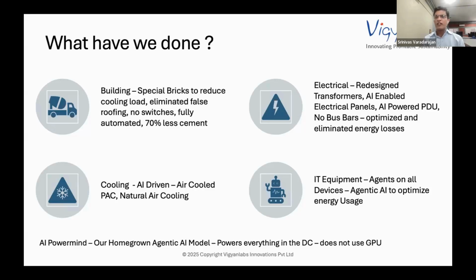All the building data centers had false ceilings. I said, why do you need a false ceiling? We found, okay, you do the design differently. For example, false ceiling is there to conceal the wires and trays. Can we cast those pipes and sensors in the roof itself? So we cast the roof. That way you eliminate the false ceiling, and at the same time you also reduce the height by 1 foot. Then we eliminated switches.